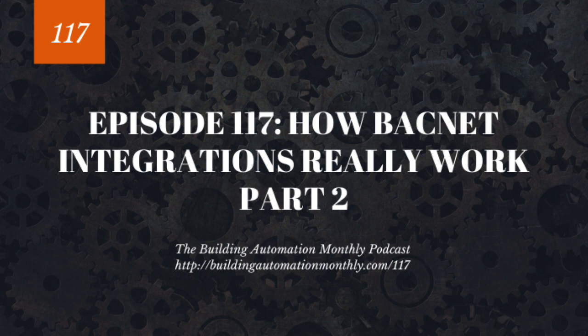Now, troubleshooting. How do you troubleshoot BACnet MSTP? I was in the military. I worked on missile systems. I know how to use an oscilloscope. I know how to do metering. I know how to run down comm errors. But the first thing I do when I have MSTP issues is I don't stick a scope on it. I don't sit there and start metering it. That's not what I do. The first thing I do is the duplicate check. Does it have a duplicate MAC address? Does it have a duplicate device ID?